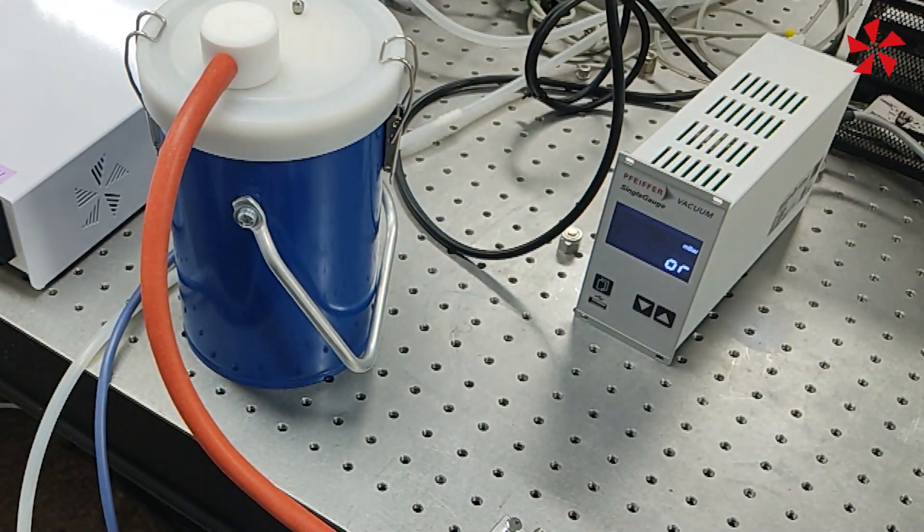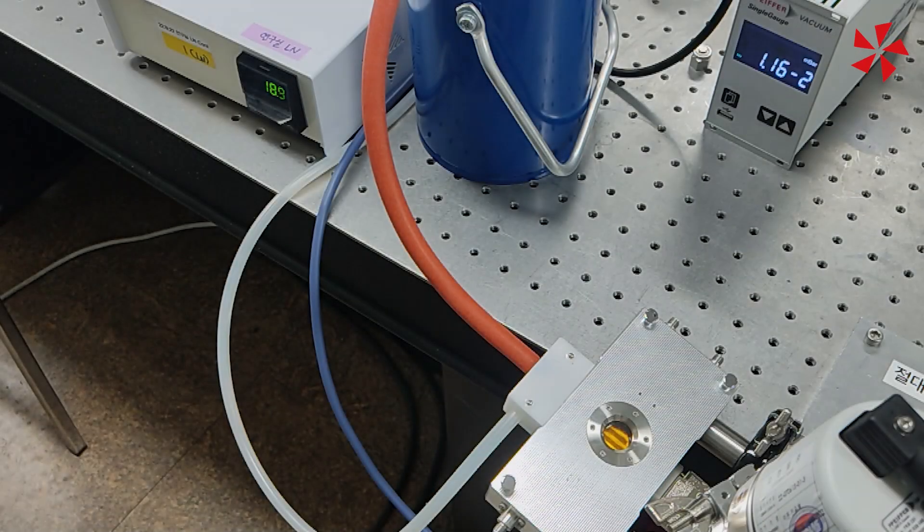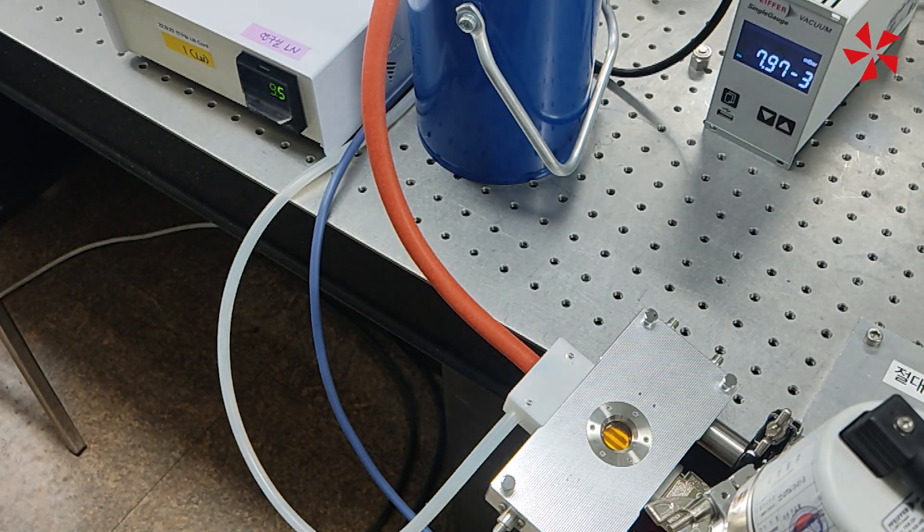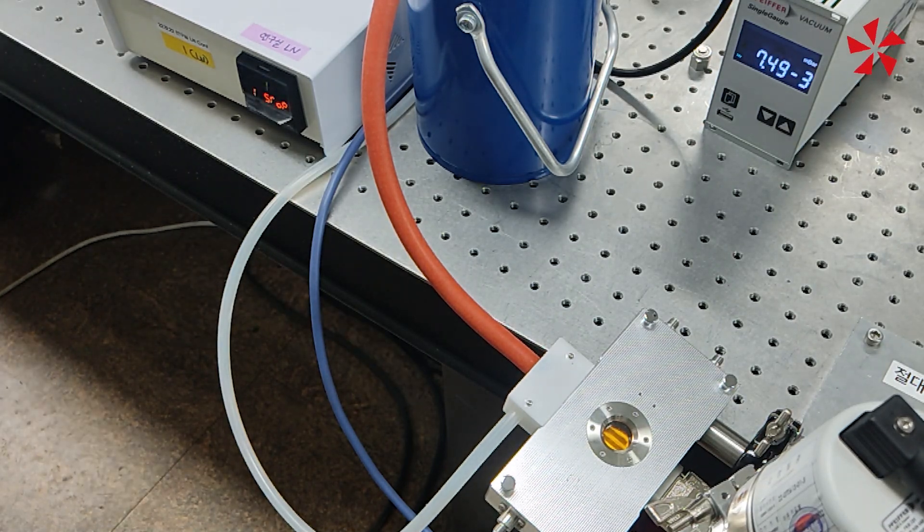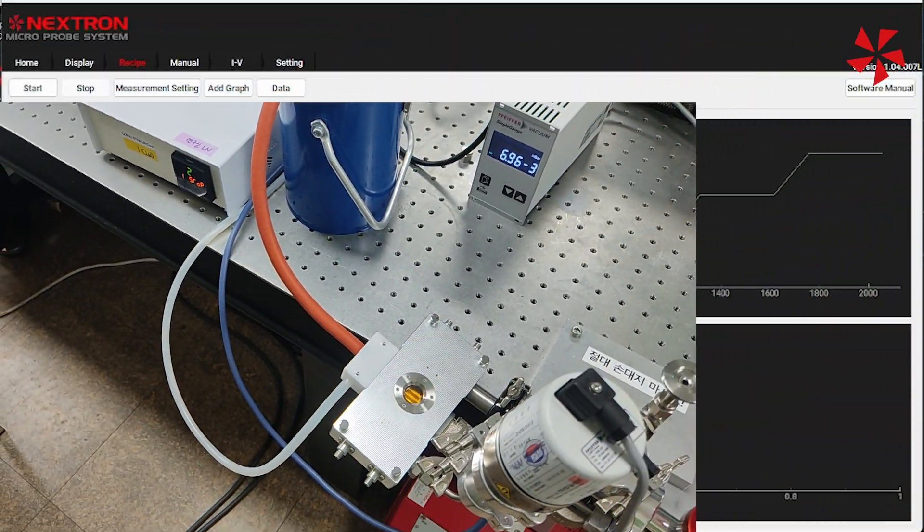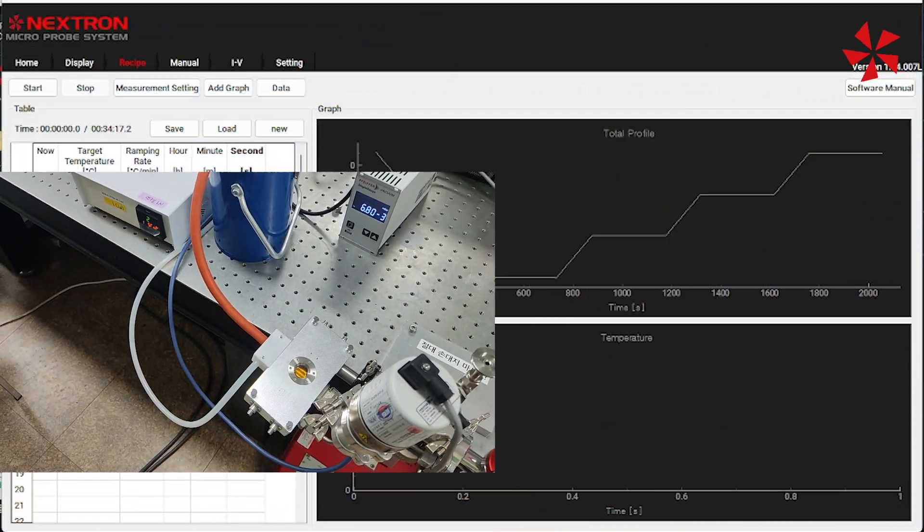Second, use a pump to make the chamber vacuum. This time we will make a vacuum rate around 10^-2 to 10^-3 millibar, same as last time.